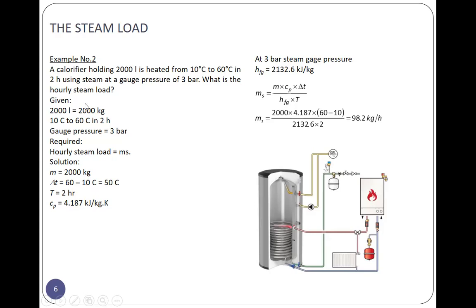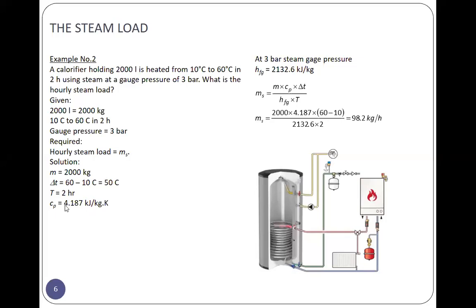So what is the hourly steam load, given 2,000 liters, which is equal to 2,000 kilograms? This is water, right? The density is 1 kilogram per liter. So 10C to 60C in 2 hours at this pressure. Required: the hourly steam load, M_s. So t is 2 hours. Cp is 4.187 kilojoule per kilogram Kelvin. At 3 bar steam gauge pressure, h_fg is 2132.6 kilojoule per kilogram, from the steam tables.